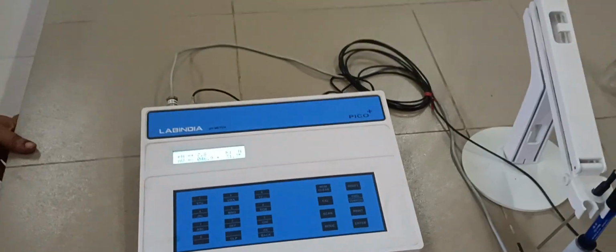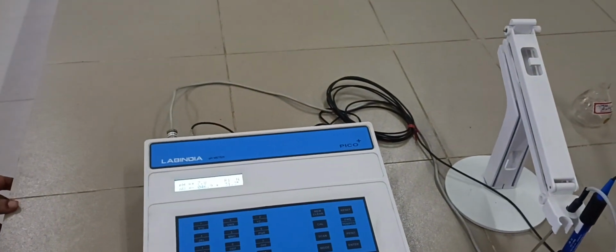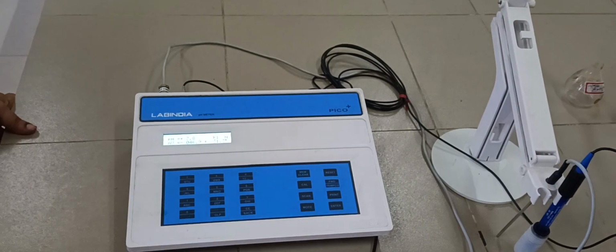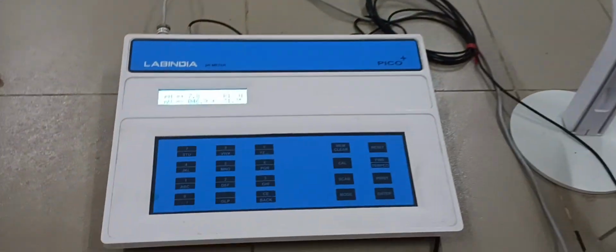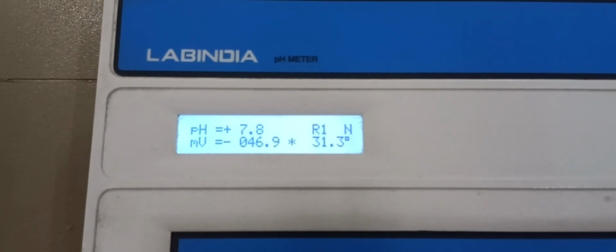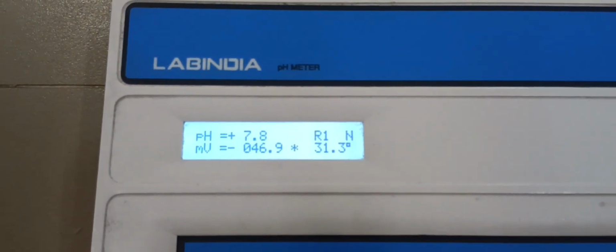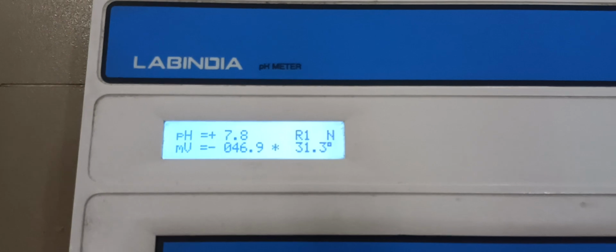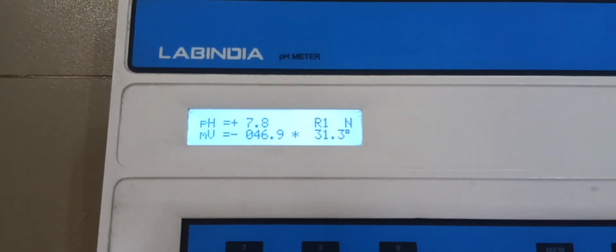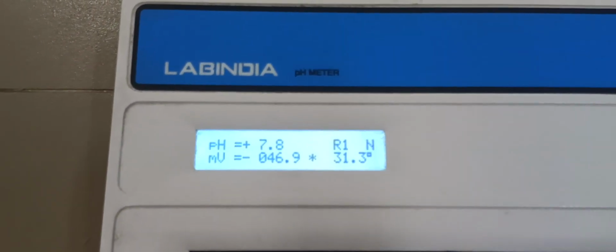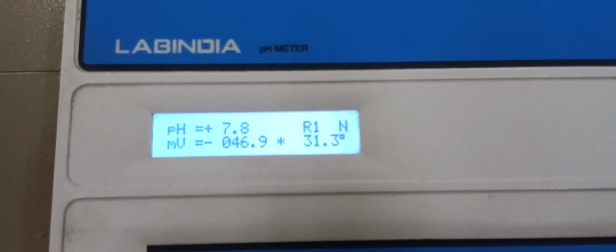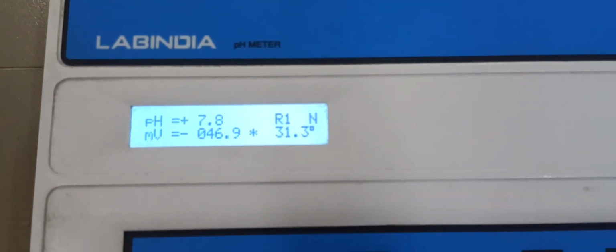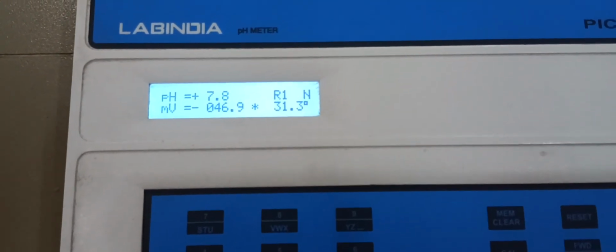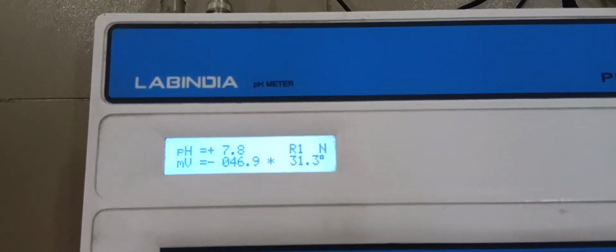Our experiment is the calibration of the pH meter. In calibration mode, the letter R is present. R equal to N means no calibration, that is, this instrument was not previously calibrated. If any letter other than N, any alphabet from A to Z, is present, the instrument was already calibrated. If R is equal to N, it means the instrument was not calibrated previously.